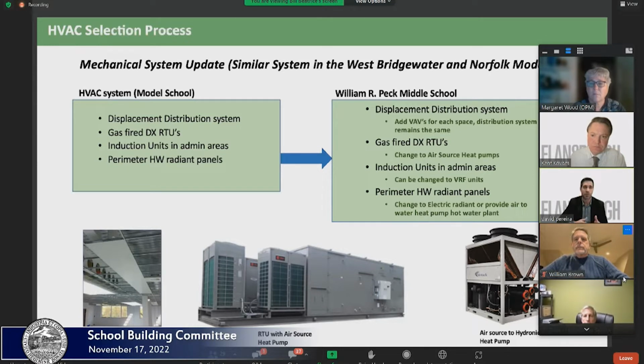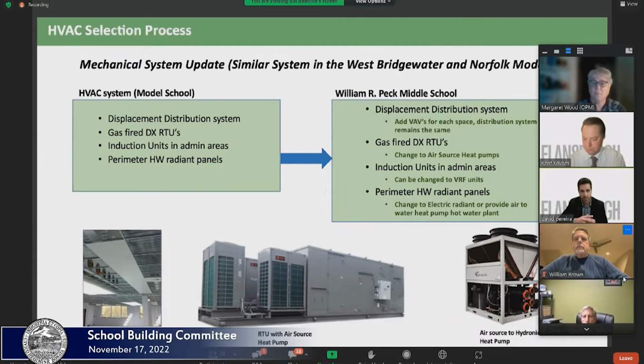The distribution system would remain mostly the same, with the addition of VAVs for each space for better temperature control and energy efficiency. The rooftop units would need to be changed to air source heat pump type, or you could use air source or hydronic heat pump systems as a central plant. Induction units could be replaced with VRF units, or induction could be paired with a hydronic central plant, same with the radiant panels. They could be electric or hydronic and paired with the hydronic central plant as well.